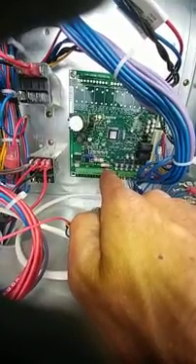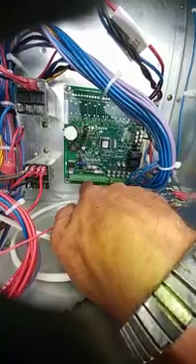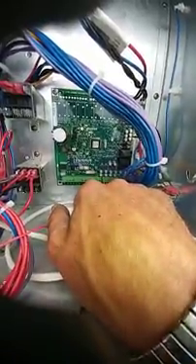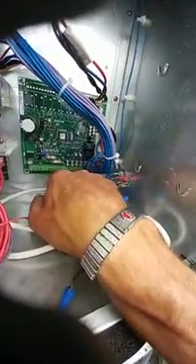Pretty simple basic wiring. You also have the option for Trane remote sensors — we have two units here with those and it's even easier: you just match your numbers up. You go downstairs — seven, eight, nine, ten, eleven, twelve, fourteen — and then you come up here and match your exact wires. They look kind of freaky when you first see them but they're not too bad. You just put them to the terminal — down there it'll be like seven, so you run red to seven, red to seven. It doesn't matter what color wire you run, just matters that you land them on the same terminal.